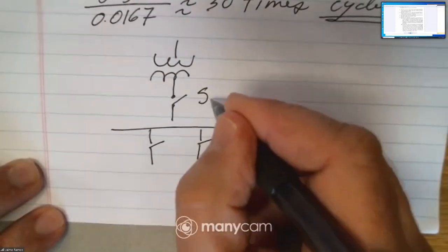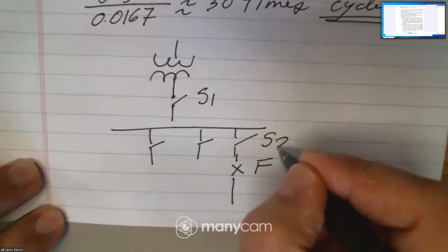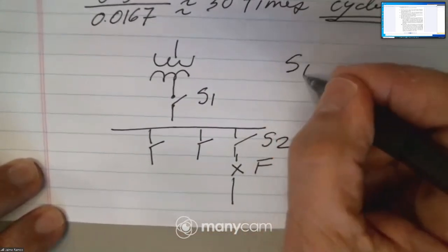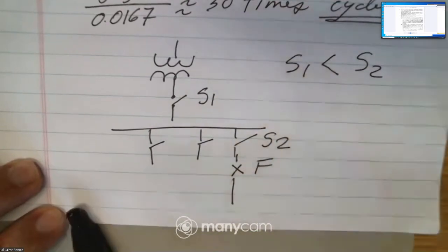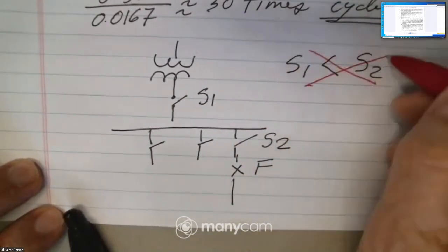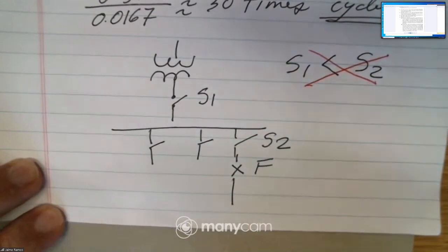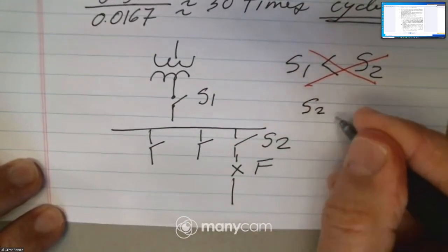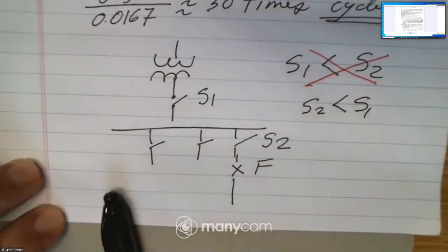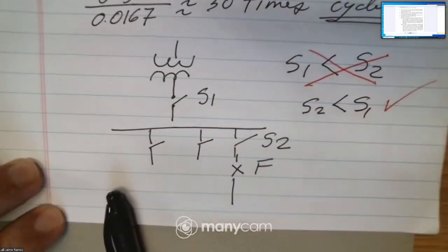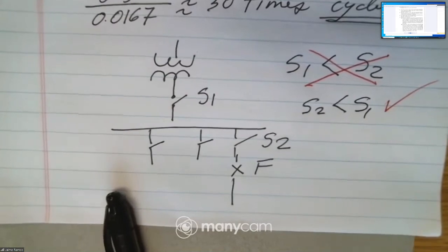So switch 1, switch 2: switch 1 before switch 2, no. Switch 2 before switch 1, yes. So that's what they mean by coordination.